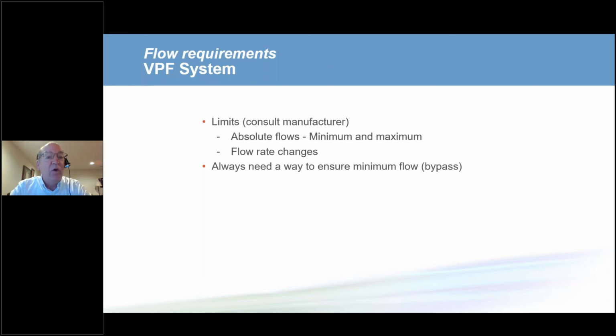If we go below the minimum flow rate, as I said, our efficiency gets bad, our heat transfer gets bad, and we can reduce the suction temperature and pressure in the evaporator so far, because the approach temperature gets bad, that sometimes in the past people have done it poorly, and decades ago they froze the tubes in their chillers. We know how to take care of that today. The second thing is the chiller unit controls need to be able to respond to flow rate changes. So if you're going to do variable primary flow, particularly on an existing chiller, contact the chiller provider to make sure that his or her chiller can operate at different flow rates. And you want to know how fast the flow rate can change.